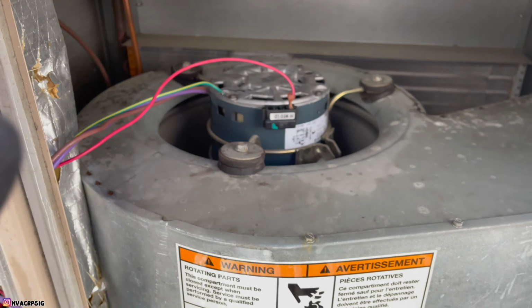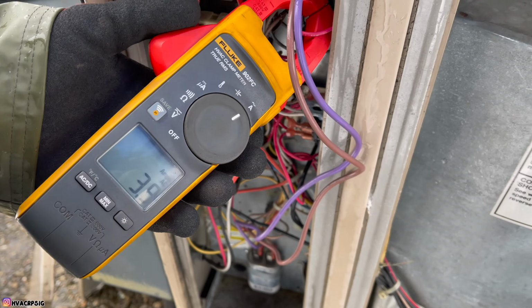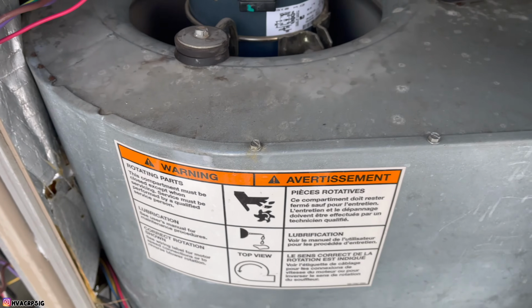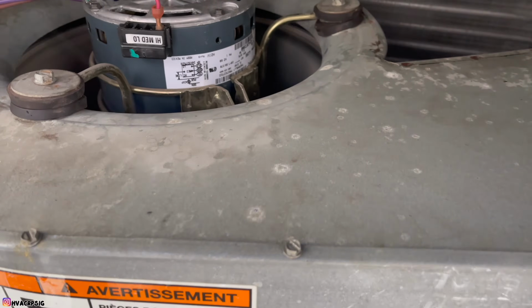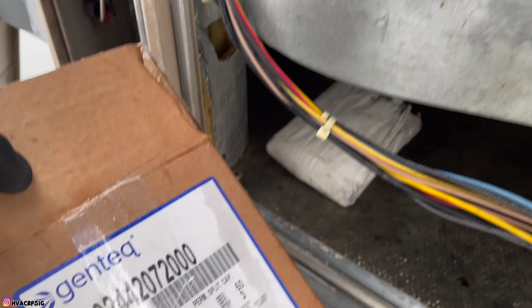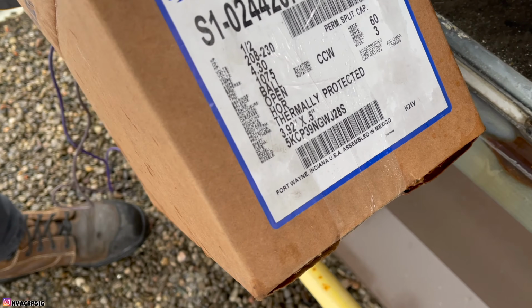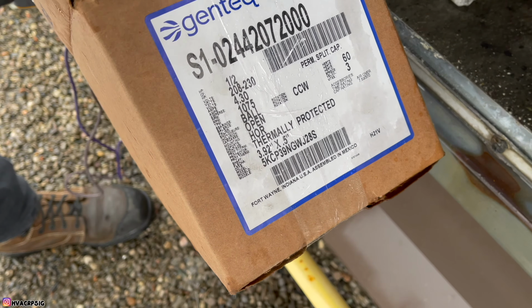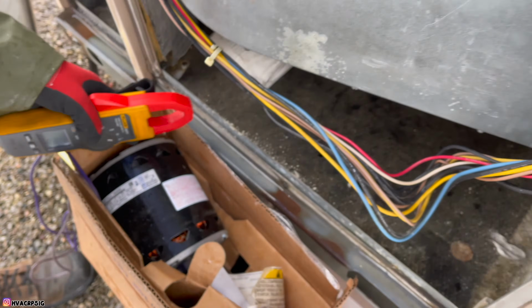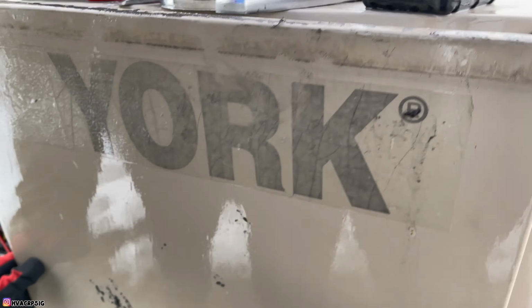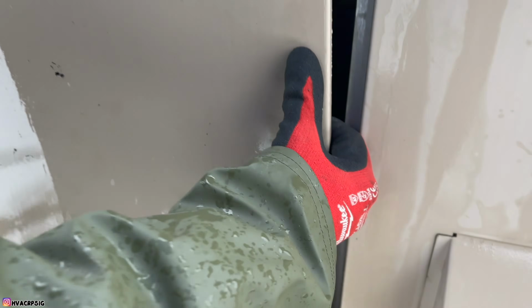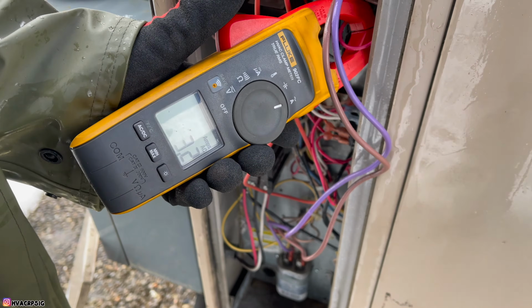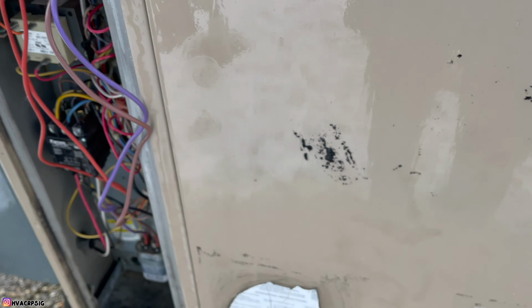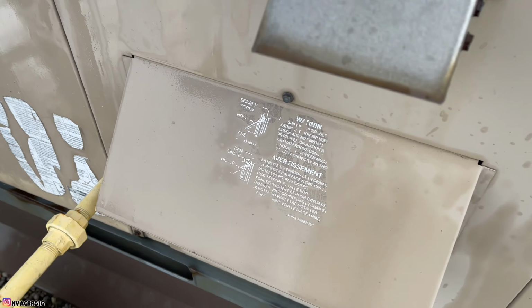Looks like our rotation is good, which it should be. Running about 3.9. And doors open. Doors open, 4.3 max. Technically 3 speeds, but we only have those wires for the high speed. So fan on enough. There we go. We dropped down to 3.2. So we're dropping amperage because we closed the door and it's doing less work.